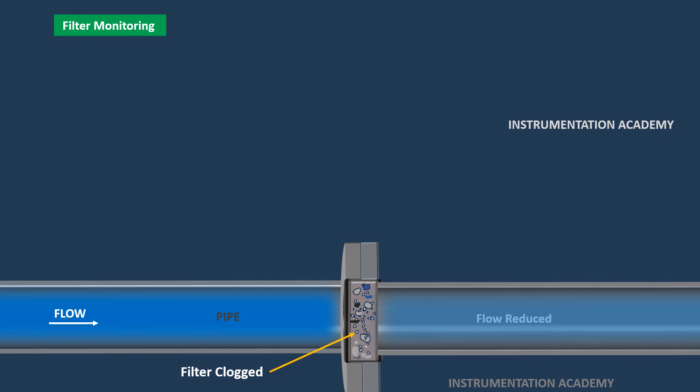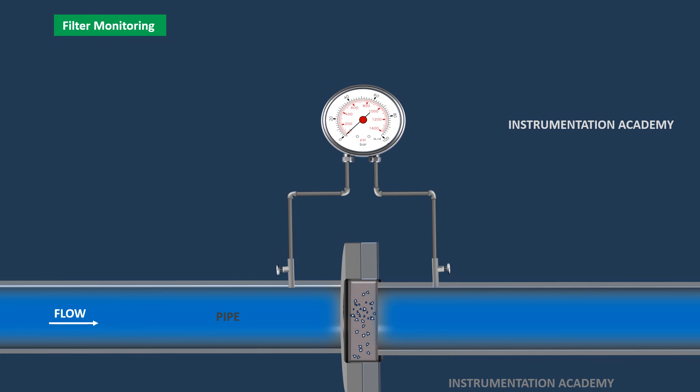To monitor the filter's condition, a differential pressure gauge is used. Pressure taps are placed at two points, one before the filter and one after the filter. These taps are connected to the differential pressure gauge, which continuously measures the pressure difference between the two sides of the filter.